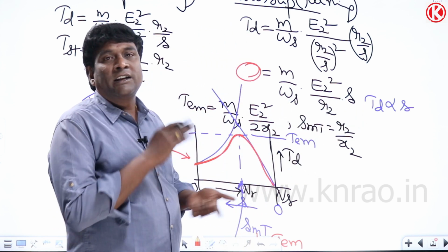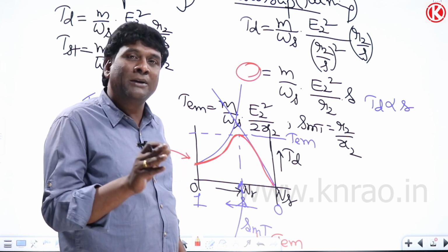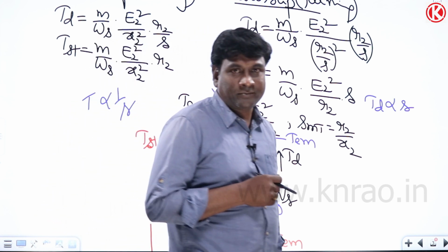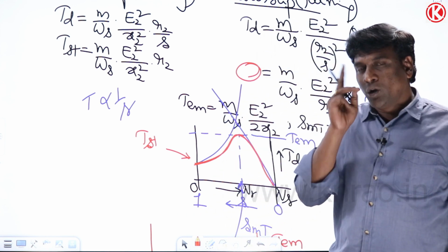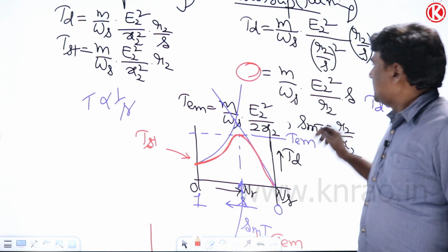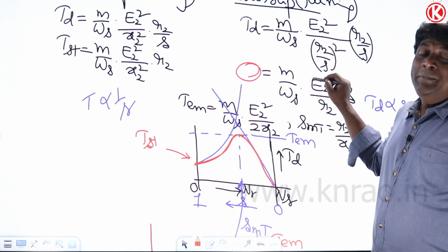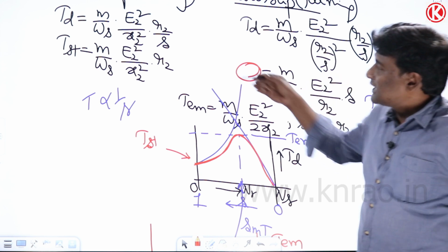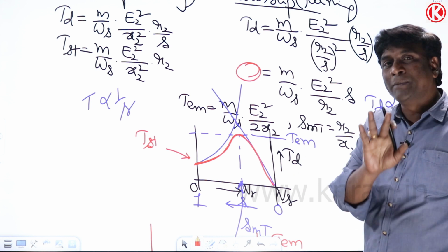Such that the torque requirement of the load has to be furnished by the motor. In this condition, only one point you have to keep in mind: the running torque requirement will be decided by the load. Starting torque and pull out torque will be decided by your motor.